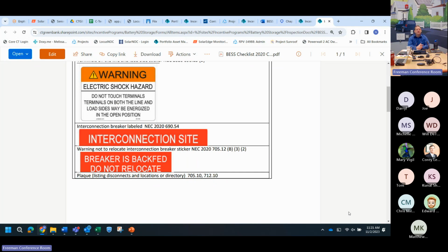Just like with a solar PV system, you need to label your point of interconnection. For example, if you're interconnecting into a main panel behind a breaker, which happens even with newer systems, you want to label that breaker. Because that breaker is likely to be at the bottom of the box, using the 120% rule and all the things you'd expect, you want the future electrician working on the box to not relocate that breaker, because you don't know who's going to come in behind you.